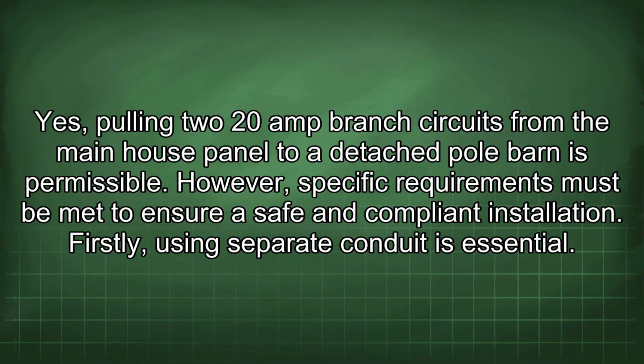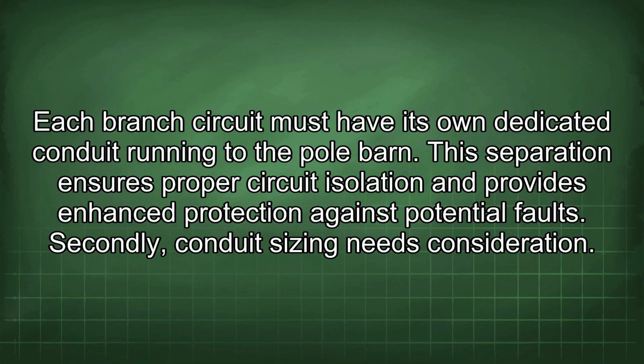Yes, pulling two 20-amp branch circuits from the main house panel to a detached pole barn is permissible. However, specific requirements must be met to ensure a safe and compliant installation. Firstly, using separate conduit is essential. Each branch circuit must have its own dedicated conduit running to the pole barn. This separation ensures proper circuit isolation and provides enhanced protection against potential faults.